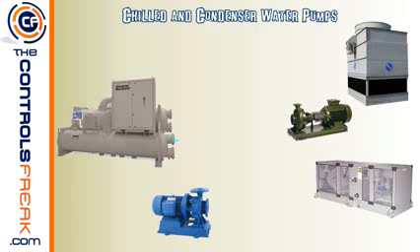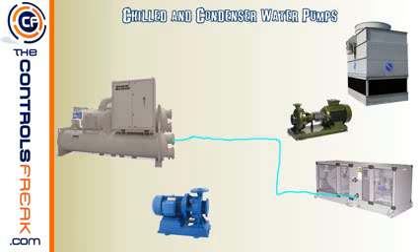The chilled water piping comes out of the chiller in light blue — it's cold — and enters the bottom of the coil. It's important to pipe the incoming water to the bottom of the coil so it fills from the bottom up, with the outlet at the top. This ensures the coil fully pressurizes with water and pushes out any air. If you supplied from the top, air could get trapped in the coil and reduce cooling effectiveness in the upper portions.